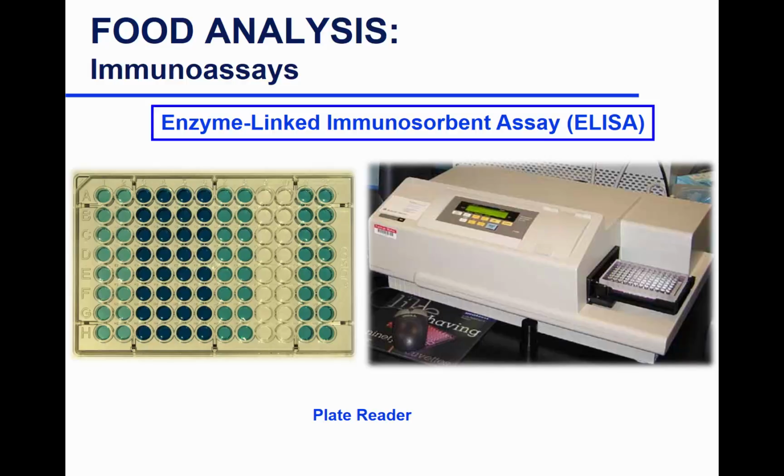So you can add your reagents plus a standard curve all in one plate, and then this would be a spectrophotometer, but instead of a place for a tube or a cuvette, you will have a place to insert your whole microplate, and it goes in, and absorbance in each well is read simultaneously. It's a very effective way of running an assay, where you can do tens of samples in one shot.